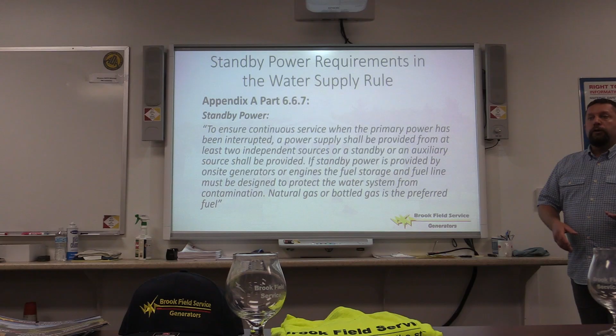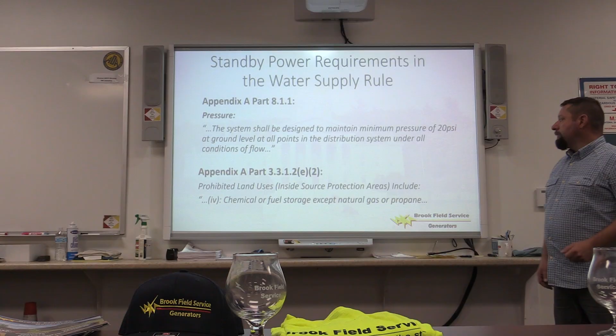And the other thing too is natural gas or propane is the preferred fuel. If you have a gas generator, just be aware that if you have a well, within that 200-foot protection area around a well, you cannot have gas or diesel. The other thing too, as we all know as water operators, is you need to maintain 20 PSI at ground level at all points within the system. So if you have pump stations, or hydropneumatic tanks that keep pressure in your system, having access to a generator when losing power will help you keep that 20 pounds so you do not have to go into a boil water notice or do not drink or whatever may happen. And as I said, chemical fuel storage, except natural gas and propane, is not allowed within the 200-foot radius of that wellhead or source.